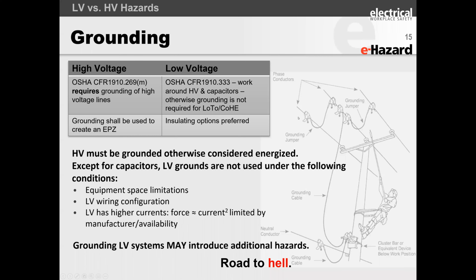What that means is whatever happens to the system, everything's going to move appropriately. I'm going to talk about this in the next, we'll move with the same potential. All right, means that if voltage 1 minus voltage 2 is 0, then you're not going to have any current through this worker's body. So the high voltage rules want you to apply grounding in such a way that you establish this equipotential zone, EPZ.